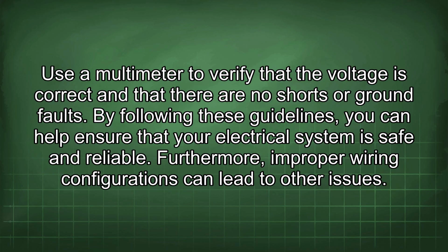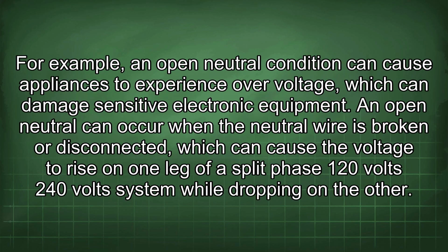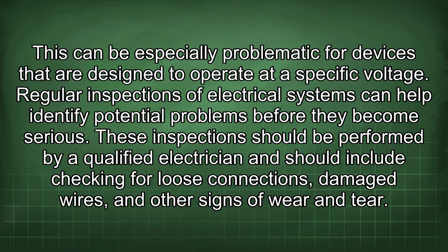Furthermore, improper wiring configurations can lead to other issues. For example, an open neutral condition can cause appliances to experience overvoltage, which can damage sensitive electronic equipment. An open neutral can occur when the neutral wire is broken or disconnected, which can cause the voltage to rise on one leg of a split-phase 120-volt 240-volt system while dropping on the other. This can be especially problematic for devices that are designed to operate at a specific voltage.